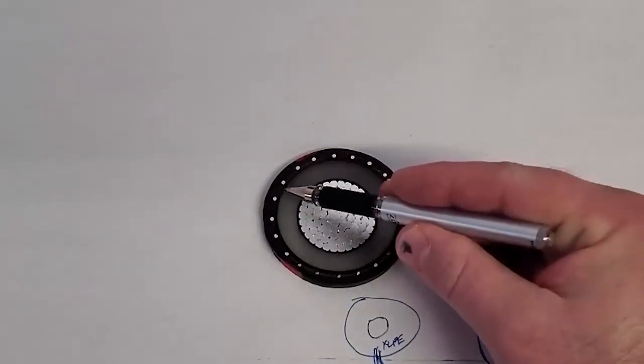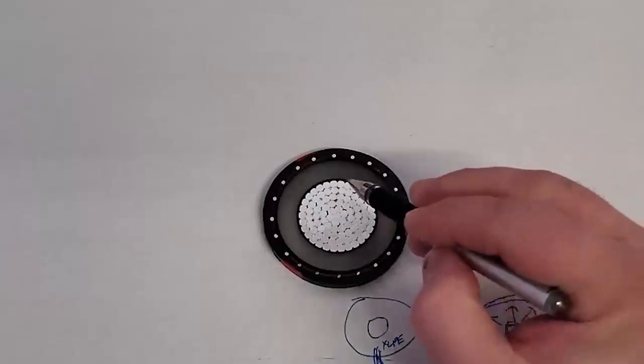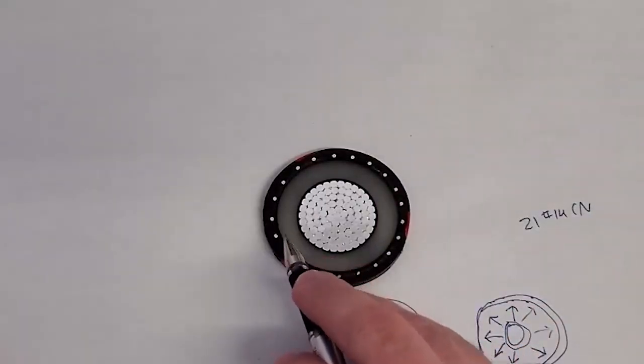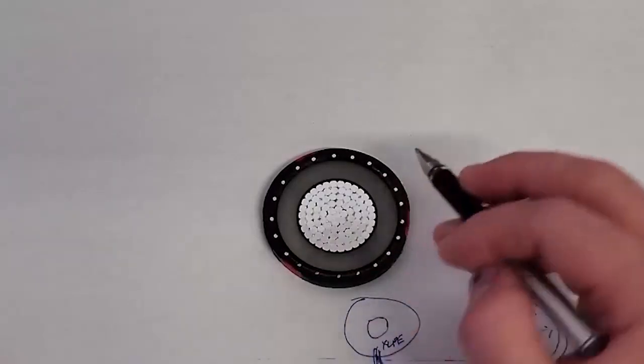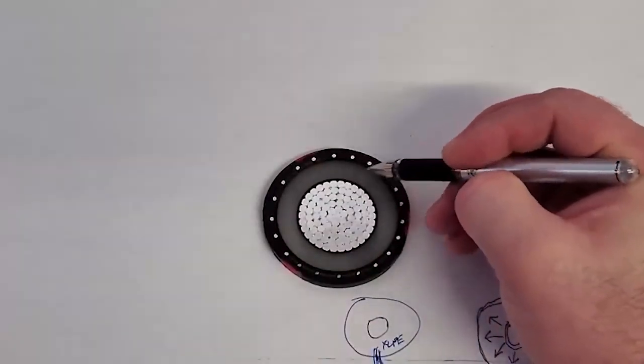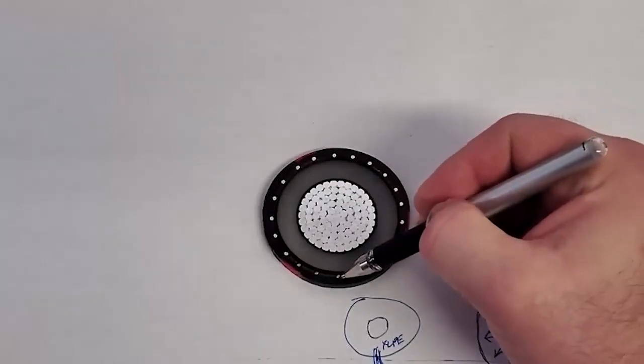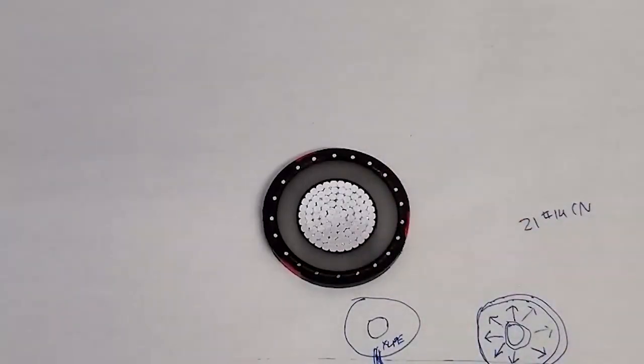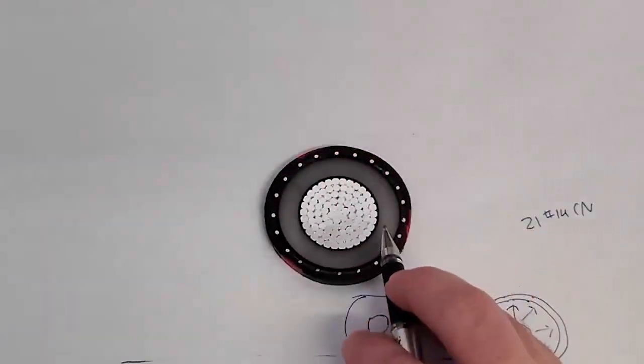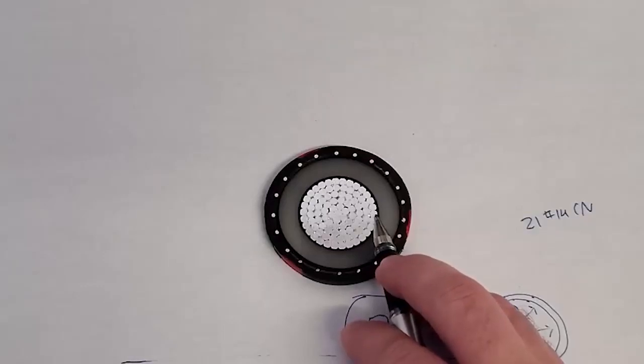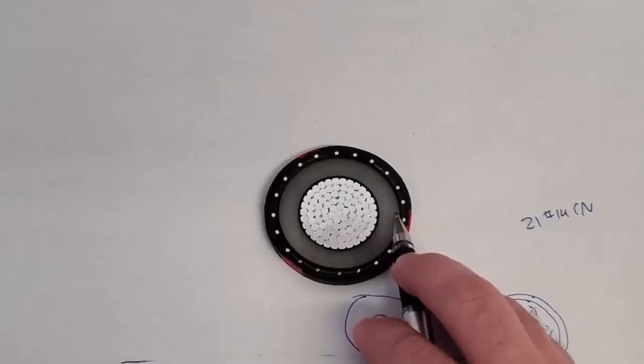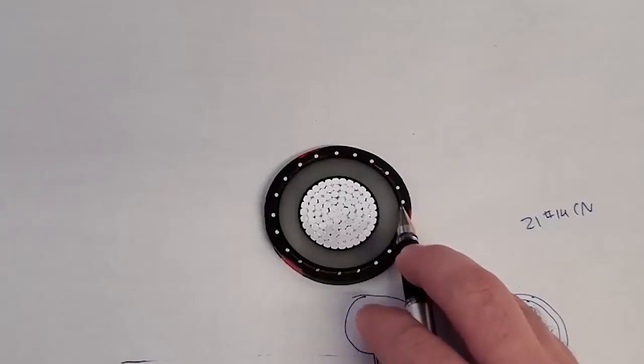This layer basically keeps this insulation shield grounded. Again, it's evenly distributed around that semicon layer. So as the lines of flux bleed through the insulation evenly, they're ultimately bleeding to these concentric neutrals, which at the terminations on either side are grounded. So this is the actual grounded layer. So it's pretty crazy to think about it. Between this energized conductor that has 20,000 volts on it, 19,900 to ground, which is 35 kV 3-phase, you only have a little bit more than half an inch to ground.